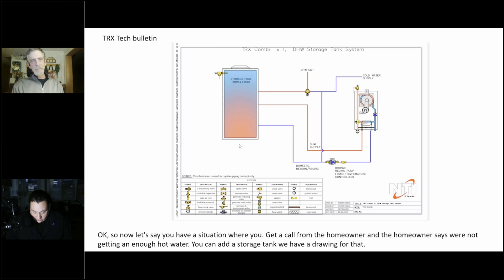If you wanted to do an electric hot water heater, just imagine you have right here the aquastat. It's a live voltage aquastat. There's always one at the top of an electric water heater, and always one right down here at the bottom. What you want to do is disconnect this one and wire this one in. This pump here is your key. This pump creates flow. So you'll wire this pump in series with that aquastat.